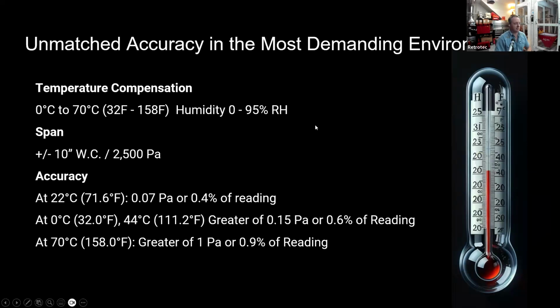The accuracy of this is pretty incredible. Like I mentioned, it's the same digital sensor that the DM32X has. When we launched the DM32X, we were able to do some software filtering on that sensor to make it extremely precise and repeatable, and we took everything from that gauge and put it in here. Even in some pretty demanding environments—if you're in a crazy hot attic—at 158 degrees Fahrenheit, you'll still be around 1 Pascal off on the reading as far as accuracy goes.